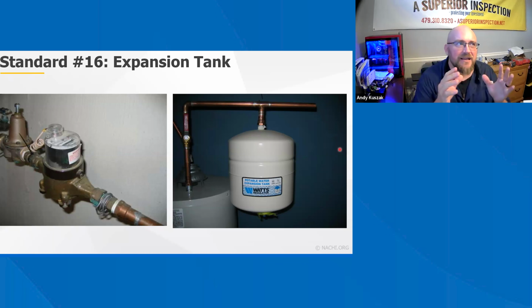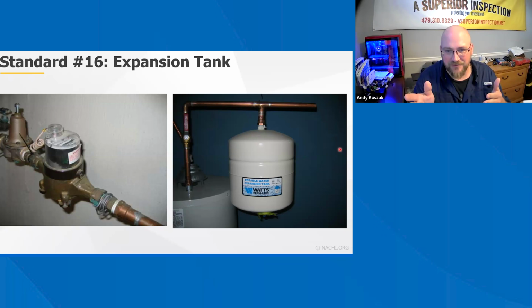So on a solo, if you just have a tankless water heater without any check valves or anything like that, then technically you don't need a thermal expansion tank, because you don't have a tank system. So the tank system is what provides the pressure.